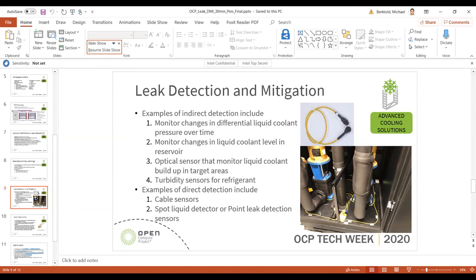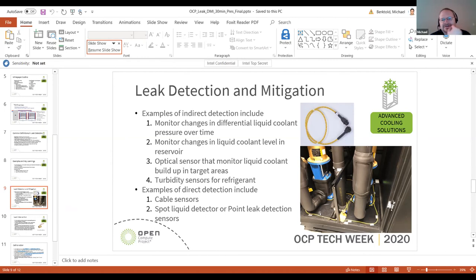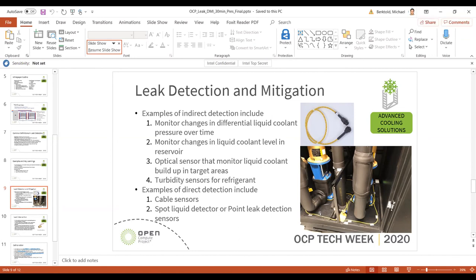Jason also asked: do you have these areas in a drain pan that leads to a room drain? Usually it's a containment pan — designed just to fill the pan, not necessarily requiring a constant drain. From the secondary loop perspective inside IT equipment, you're probably not looking at a drain. But at the facility level, that might be where you need to consider a drain for larger fluid volumes across the whole data center.